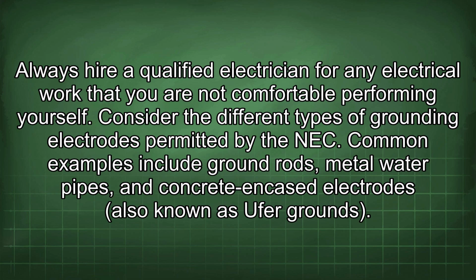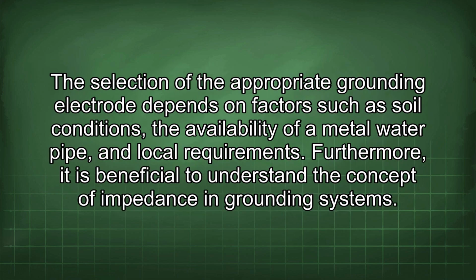Always hire a qualified electrician for any electrical work that you are not comfortable performing yourself. Consider the different types of grounding electrodes permitted by the NEC. Common examples include ground rods, metal water pipes, and concrete encased electrodes, also known as UFER grounds. The selection of the appropriate grounding electrode depends on factors such as soil conditions, the availability of a metal water pipe, and local requirements. Furthermore, it is beneficial to understand the concept of impedance in grounding systems.